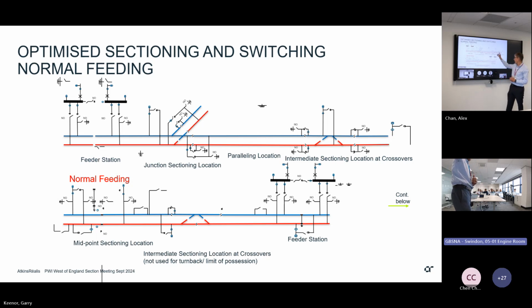But you've got a midpoint sectioning location in between, and then you don't really need intermediates, because the function of the intermediate is to provide paralleling and isolation. You can do that through a paralleling isolator and bypass around your overlaps. So we've broken it down and looked at what is the minimum sectioning required for different functions.